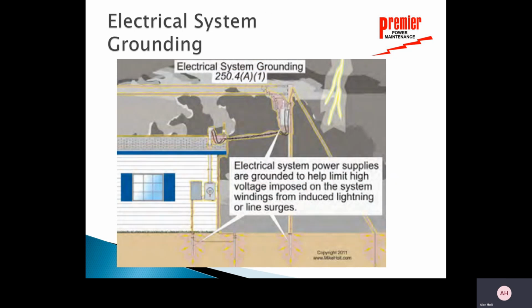So electrical system grounding. I want to make sure that I can limit high voltage imposed in the system from induced lightning or line surges. So the worst case scenario for a voltage surge typically is that lightning strike that we see here. So I've got the lightning strike that hits the power line. I've got to effectively get that to ground, and I do not want it inside my house. I want it right here straight to ground because I want to limit that voltage and clamp it right there. So that's my electrical system path that I have.